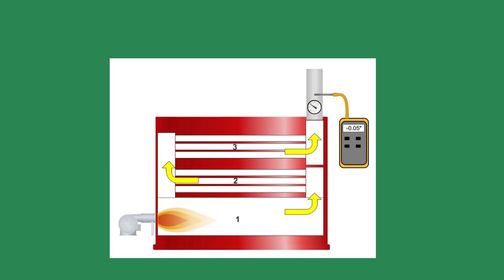The lesson I learned that day is to look at the entire system when troubleshooting. In this case, the gas pressure was set at the correct pressure, but the draft was too high. It was pulling flue gases through the boiler too quickly.